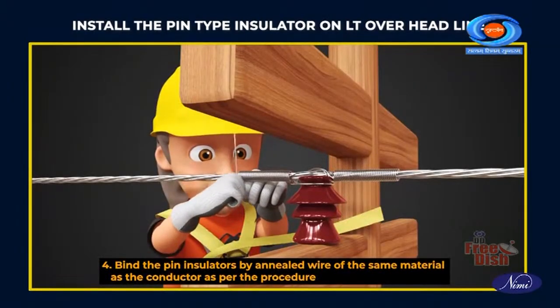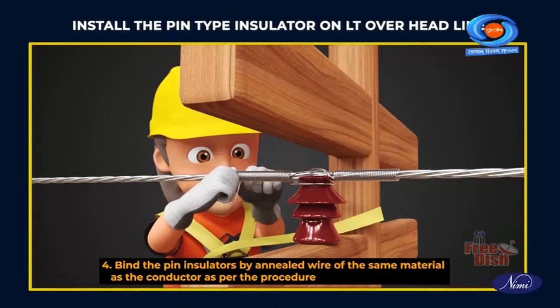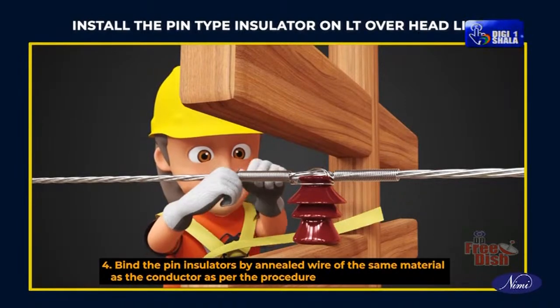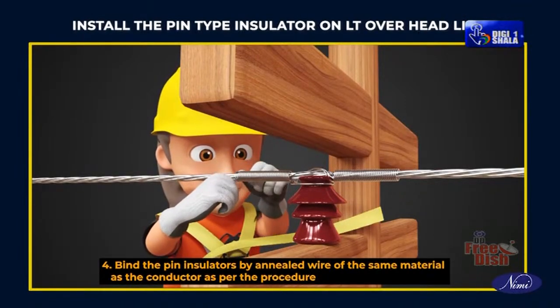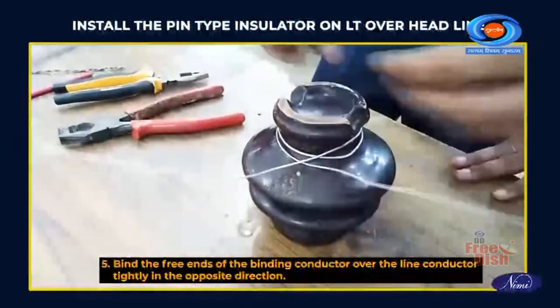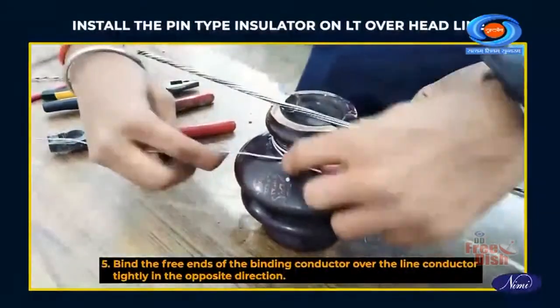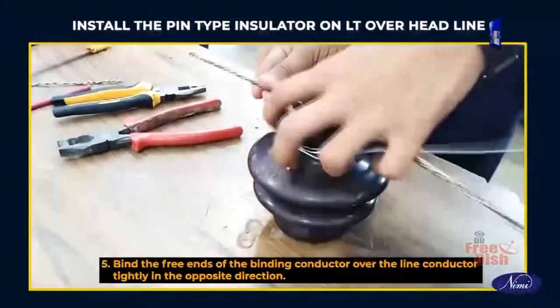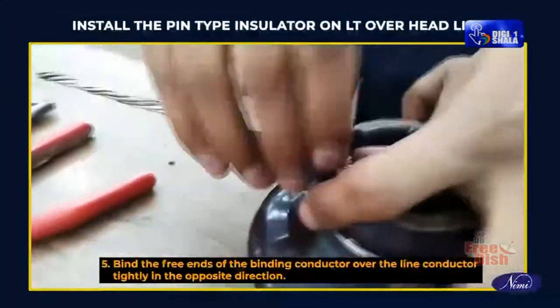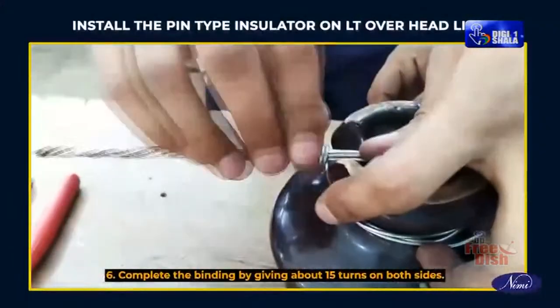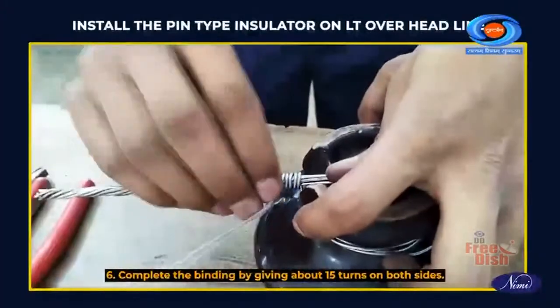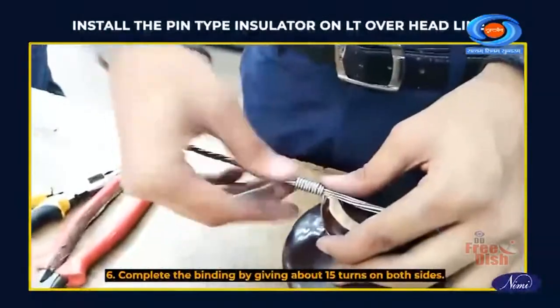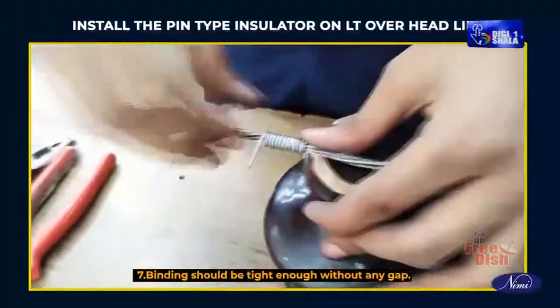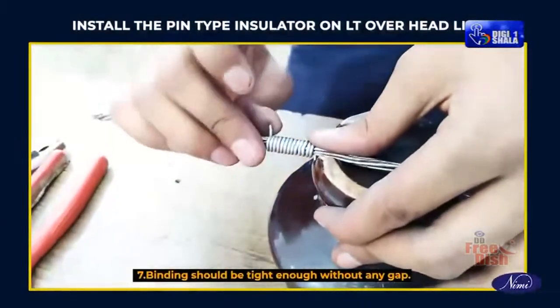Bind the pin insulators by annealed wire of the same material as the conductor as per the procedure. Bind the free ends of the binding conductor over the line conductor tightly in the opposite direction. Complete the binding by giving about 15 turns on both sides. Binding should be tight enough without any gap.